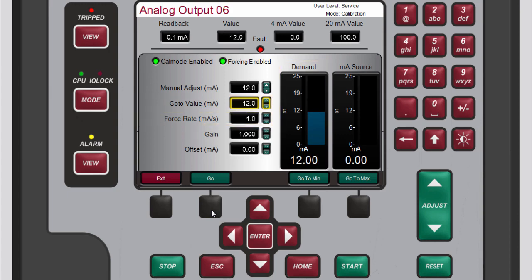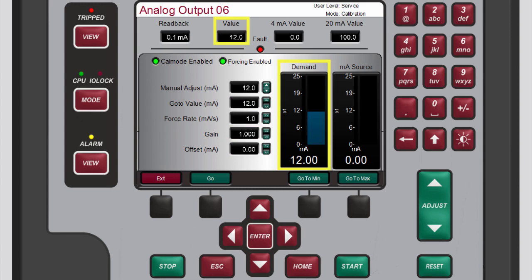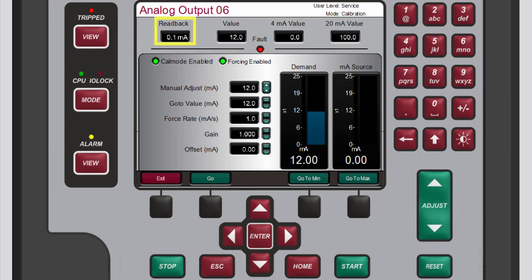The other go-to buttons can be used to drive the demand to the minimum and maximum values of 4 and 20 milliamp. You can also change the values in the gain and offset boxes to calibrate the signal. For a properly wired and functioning circuit, the demand gauge and value box should match. The milliamp source gauge and the read back box should also match. Demand is the value the software is requesting. Milliamp source is the value measured at the positive terminal for the channel. And read back is the value measured at the negative terminal returning to the channel.